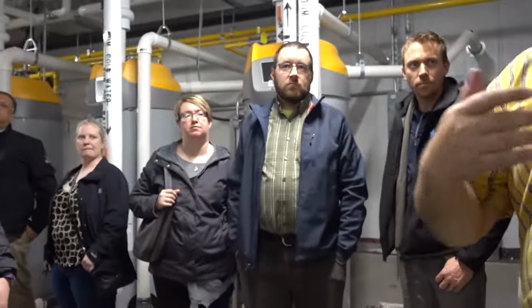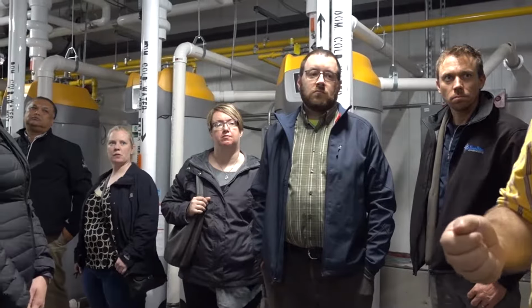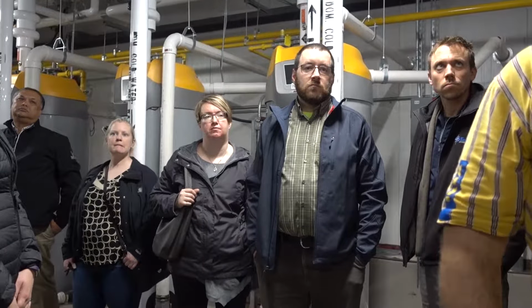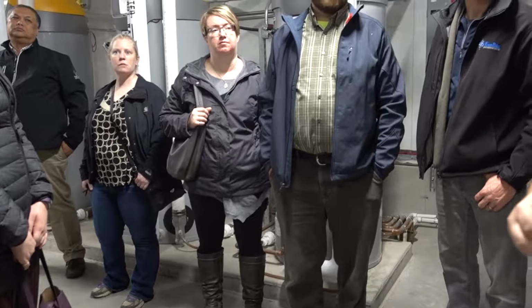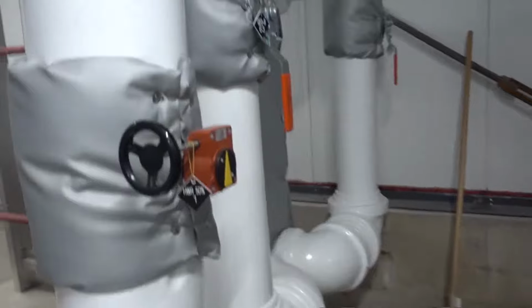As you can imagine, the total length of one loop, the heating loop or the cooling loop, is around 2 kilometers long. That much piping, lots of angles, lots of takeoffs, lots of up and down, means that we've got to maintain a constant pressure, otherwise the whole system fails. Those big expansion tanks over on the side help us do that. Finally, we have two heat exchangers for the building heating and building cooling. That interacts with the short loop in here and the loop out there.